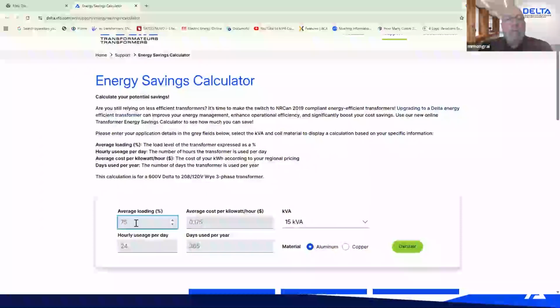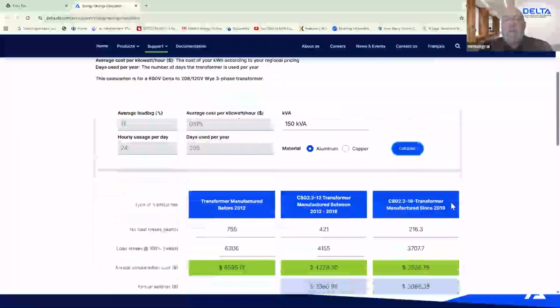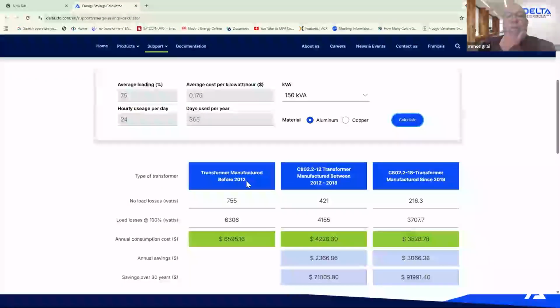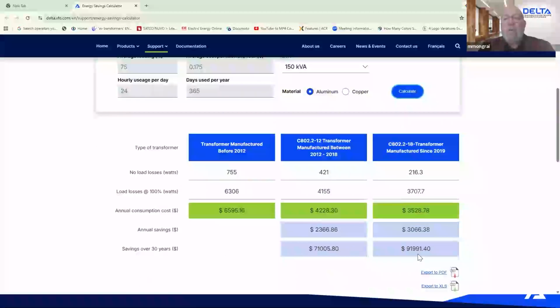But mainly you put in your average load per day, the cost of your kilowatt. So let's say it's 17 and a half cents. You use your transformer 24 hours a day, 365 days a year. You have a 150 kVA made of aluminum. You push calculate, and boom, that transformer that was built before 2012, so you have the losses. A transformer built between 2012 and 2018, which is the previous NRCan efficiency, and the current one. So based on those criteria, you're going to have your cost of consumption, or your energy cost per year, depending on the version of transformer. And then you will see what's your saving per year and over 30 years.